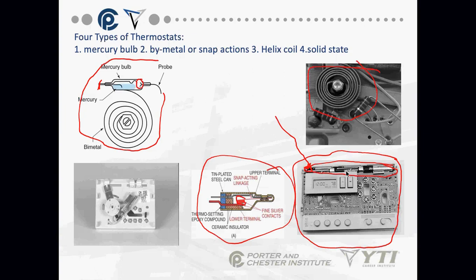I actually went and did an inspection for an insurance company about 3 weeks ago, where they had this exact style thermostat, and they didn't have air conditioning. And again, where I live, the elderly without air conditioning have some problems, even when we're talking March and February. Apparently one of the homeowners had changed out the batteries and hadn't put them in properly. They put two positives together instead of positive, negative, the way it should have been installed. Their cooling system didn't work. A contractor came out and diagnosed the entire system as needing to be replaced because of a power surge, when in reality the batteries were not in the thermostat correctly.